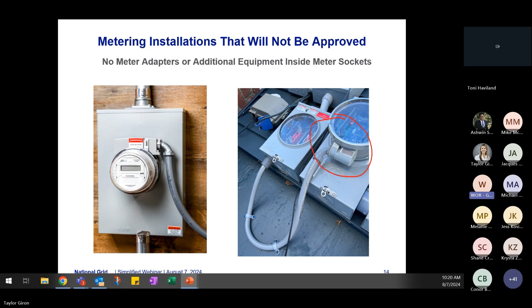Taps or splices are not allowed. A meter socket should just have the incoming line terminated at the terminals and the outgoing load side terminated at the terminals. No splices or taps of any kind inside any meter socket are allowed. And then there is also a fifth terminal for single phase 208 volt services.